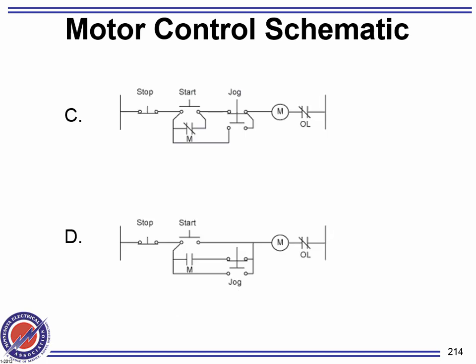What's wrong with C? Look at that. Normally closed holding contacts. Since when you get familiar with normal closed, normally open, right? No, holding contacts are normally open contacts, not normally closed. Overloads are normally closed. And then, of course, the last one is you want to focus on getting yourself a bypass. Is my bypass right in here?